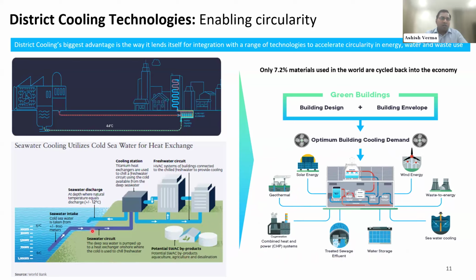Seawater cooling is very important in terms of how we design it, because it will have an impact on marine life if it is not designed properly. For example, the intake is from a bottom level. We see the temperature difference as per the level here. So it's 6 degrees at the bottom. We take the 6 degree water, and then it is discarded after utilization through a titanium heat exchanger, because seawater and the normal water cannot be mixed, as it is corrosive, obviously. So we have a different metallurgy here. Titanium heat exchangers are used, and the warm water is discharged at a depth where it is equal to the sea temperature of the same 12 degrees. So this is how the systems are designed, and we have an operational plant in Bahrain where we have the seawater cooling.